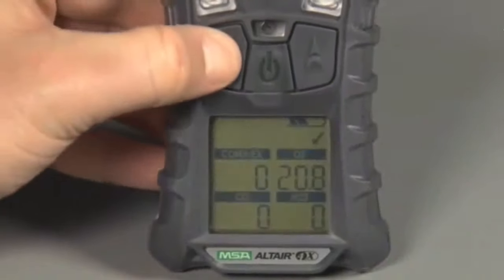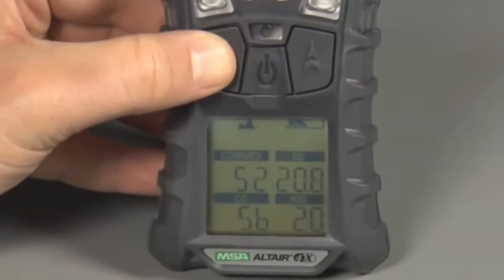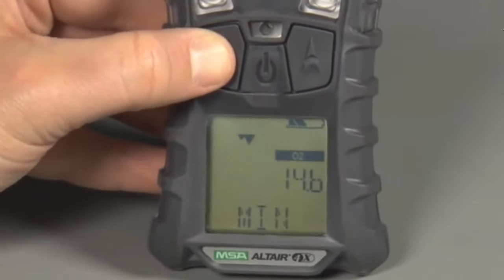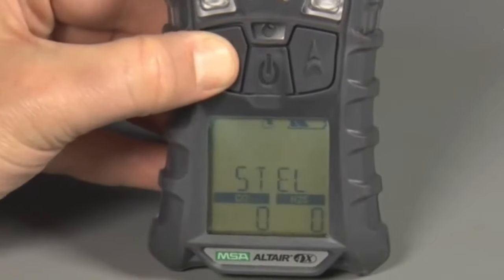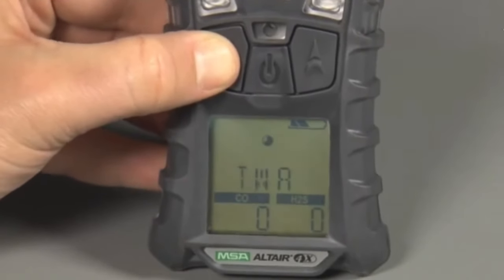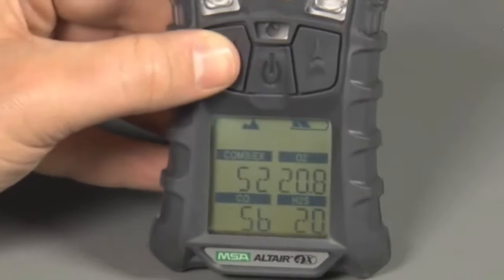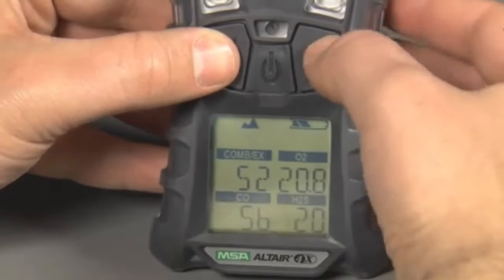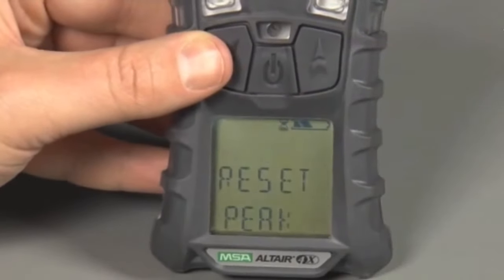Using the Page Down button after the Bump Test page, Peak Reading, Oxygen Minimum Reading, STEL, and TWA pages are displayed, each page shows current values. To clear and reset any of these values, simply push the Page Up button when the value displays.